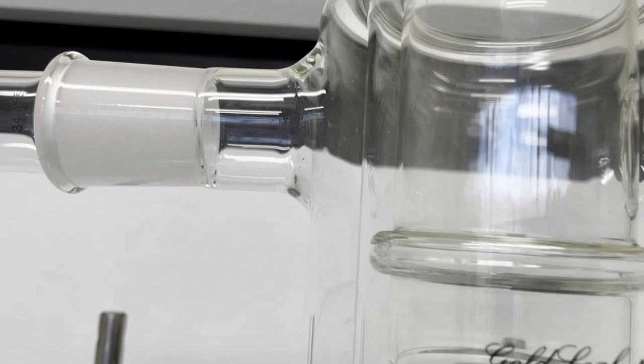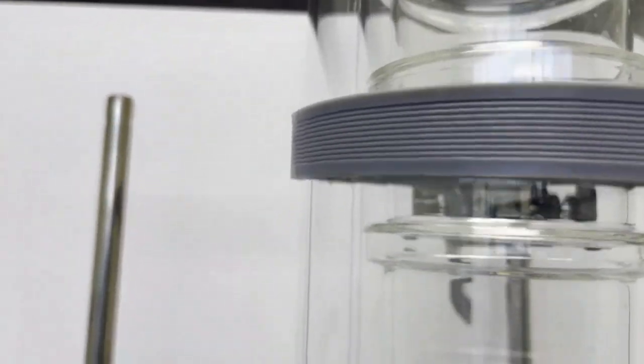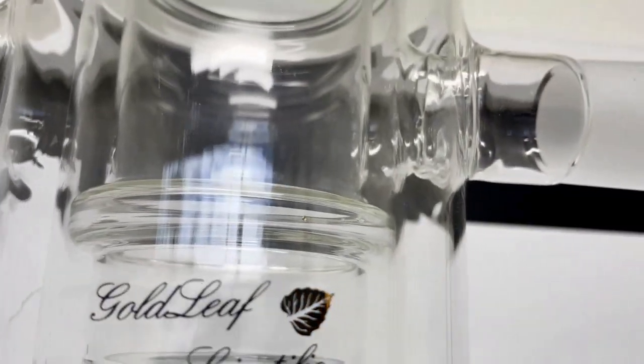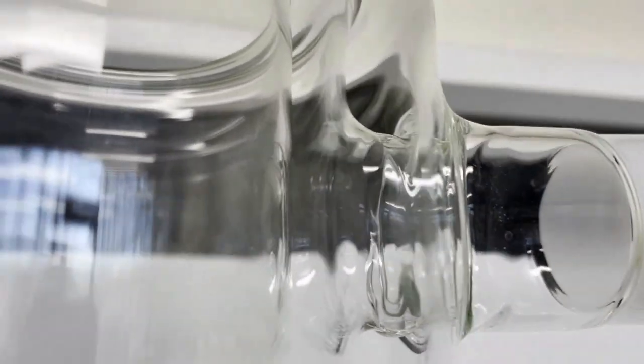condenser. The dewar cold trap is used with dry ice and alcohol to reach below -80 degrees Celsius, meant to capture heavier volatiles that are much harder to condense. An inner wall forces vapors down the bottom of the trap, where they are pulled up the entire length of the cold finger with these ring baffles for extra surface area, capturing any volatiles left over. At the end here is where a vacuum manifold would connect.